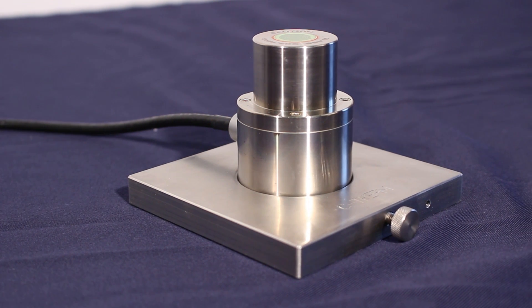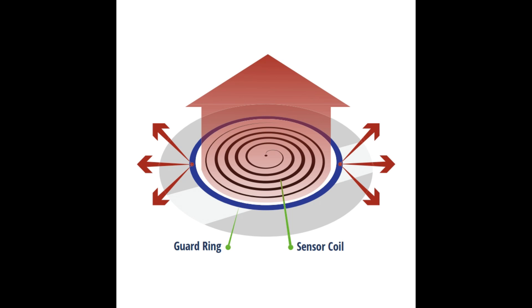What is occurring during a measurement is a small heat pulse being emitted by the sensor and a simultaneous measurement of the rise in voltage at the point of contact with the sample itself.